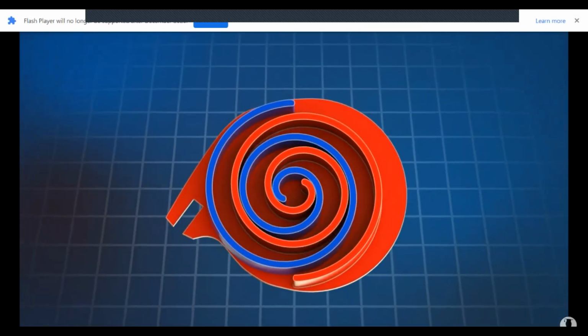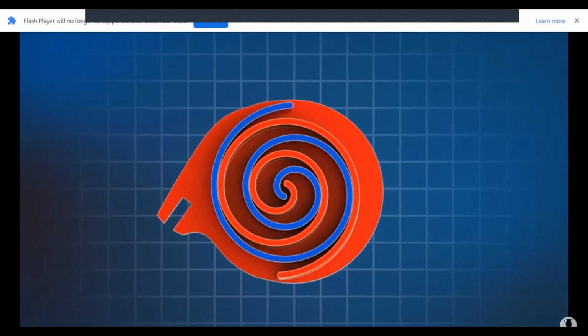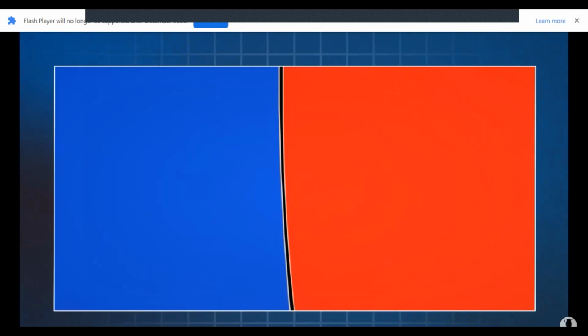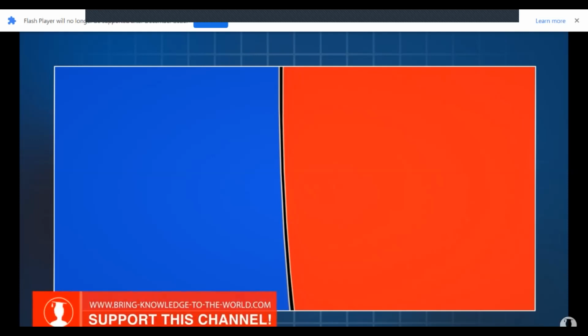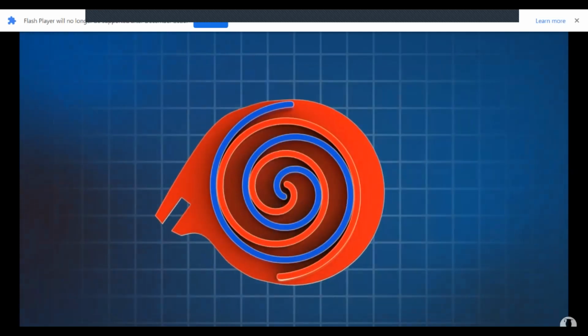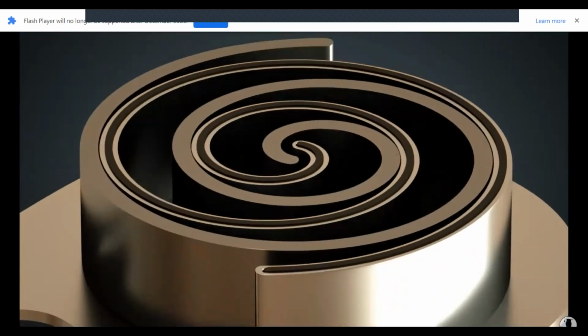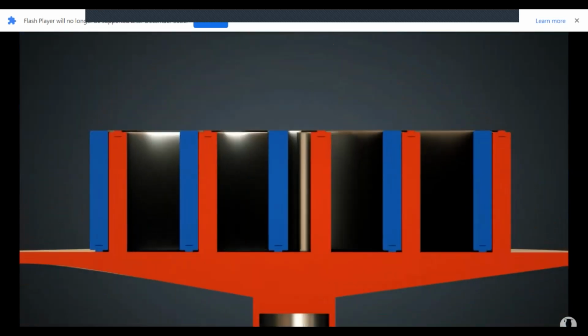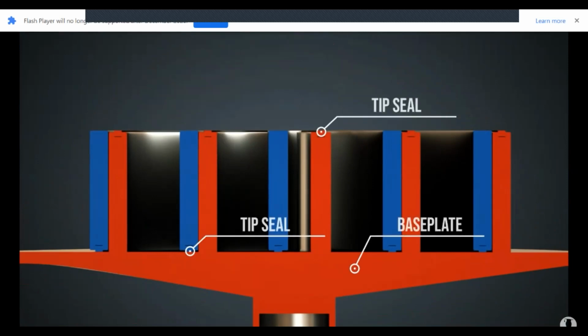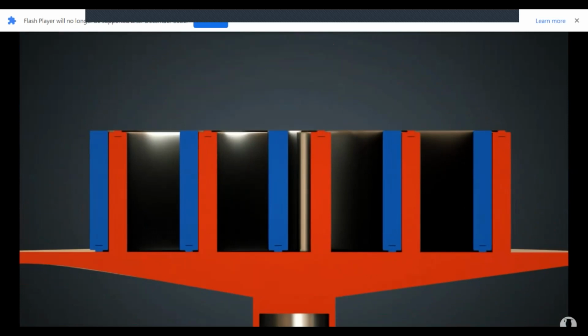Today, there are several compressor designs. On the one hand, the movable scroll can move with an extremely small distance to the other scroll. The scrolls therefore do not touch each other. On the other hand, there are also designs, in which the scrolls are in contact. Such scroll compressors usually have a better seal, and thus, a higher efficiency. Axial sealing can also be designed in various ways. One possibility is the use of a floating tip seal. These are present on both scrolls and are pressed against the base plates by gas pressure. In this animation, the upper base plate is not shown.